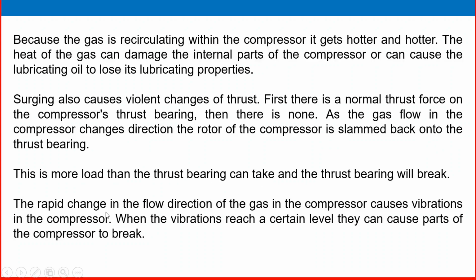The rapid change in the flow direction of the gas in the compressor causes vibration in the compressor. That is another problem. A rotating machine vibrating above the allowed level will damage the foundation system, the compressor itself, the shaft and other internal parts. When the vibration reaches a certain level, it can cause parts of the compressor to break.